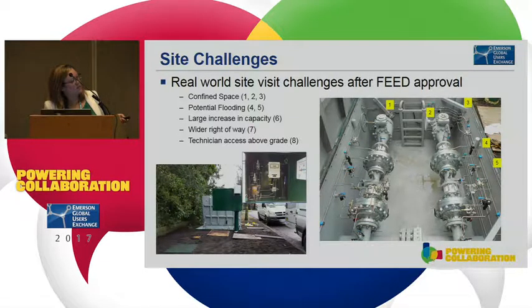One thing we did is, in the event of a flood, should that river come up or rain get excessive, we capped the sense line. All regulators need registration to atmospheric pressure in order to operate. Because they need to register atmospheric pressure, we ran that up into a tube, so if that pit should flood, there's a pocket of air that's relatively atmospheric that will continue to allow that regulator to operate whether it's completely buried or not. That's the only part of that regulator open to the atmosphere — everything else is completely sealed and contained within the device.